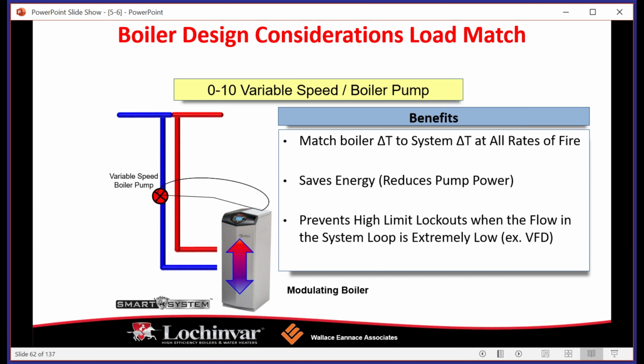So again, we have condensing and we have turndown. What the boiler is going to do is the boiler is going to modulate its fire rate. Okay, so this isn't an old school boiler where we have an on-off, right? Where we get a call for heat, the boiler turns on until it runs to whatever the aquastat tells it needs to be, and then it turns back off. Okay, or even old school 2 or 3 stage boilers where it's going to stage up and down between 25, 75, 100% fire rate, and so on and so forth. These boilers have the ability to land anywhere within their fire rate.